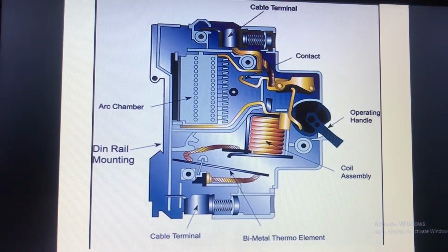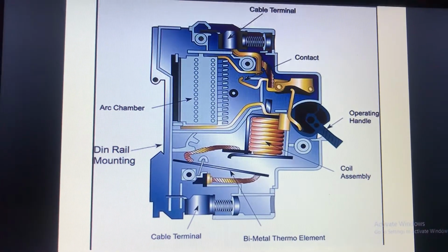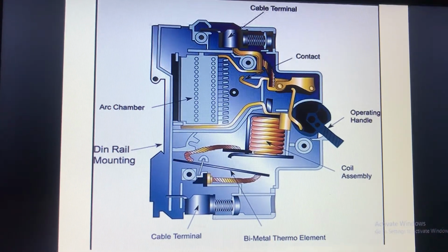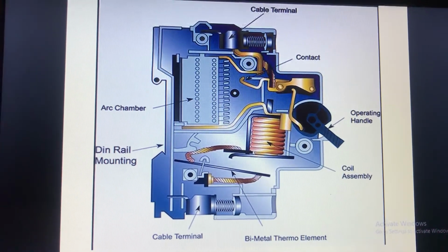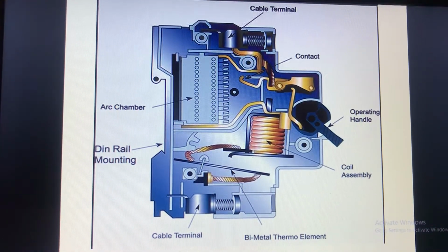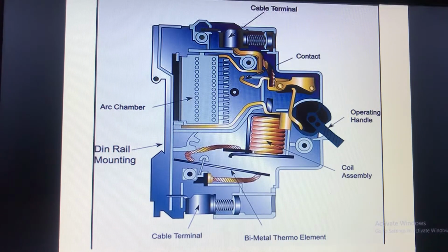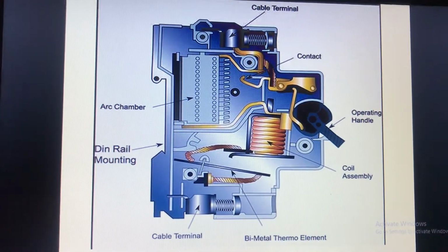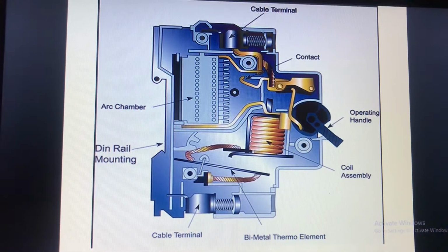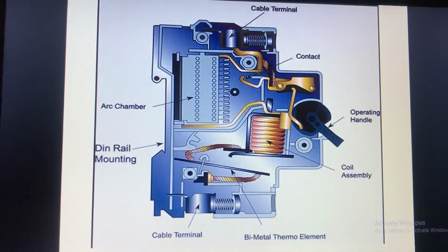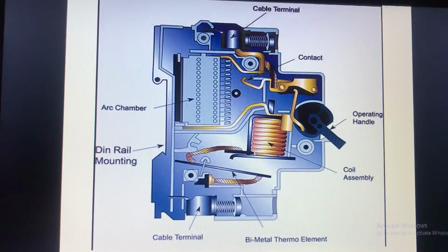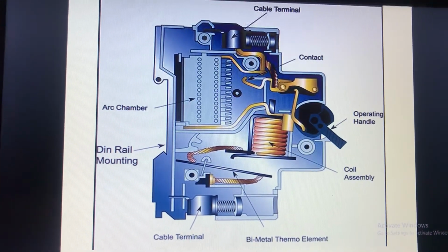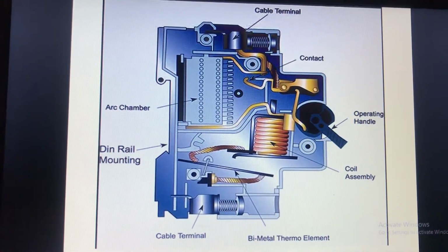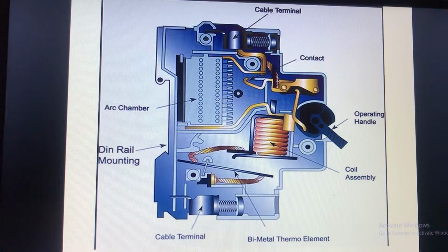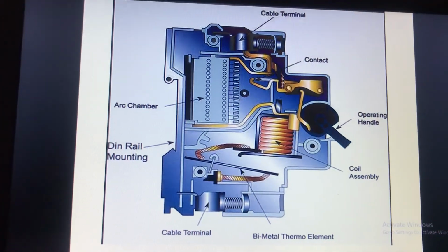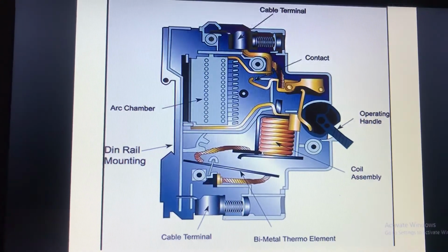So these two different protections are provided by two different elements. The bimetallic strip is for overloading conditions, and for short circuit protection, there is the coil assembly, that is electromagnetic relay, because its operation is very instant. It operates very fast as compared to bimetallic strip. Then is the cable terminal. This is output. So from cable terminal 1, input is given to the MCB, and from cable terminal 2, the output is taken from the MCB. Then is the DIN rail mounting. So these MCBs are mounted on the DIN rail. So this is the groove you can see here for DIN rail mounting.